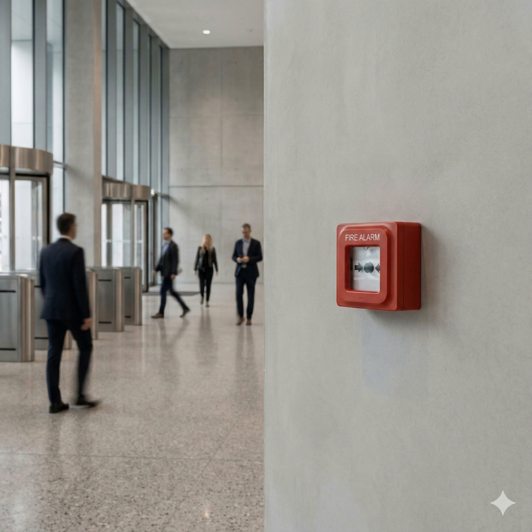Contrast that with an addressable system that reports smoke detector 14A, located in the West Utility Corridor, is in alarm. That's a huge difference. It's the difference between minutes and seconds of response time, and that's critical for containing a fire. And what about that other concept, cross-zone detection verification? That sounds like it's specifically designed to fight the nuisance alarm problem.